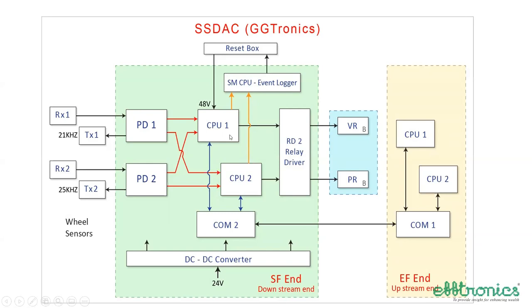CPUs. So CPU 1 and 2 of one end are communicating with the CPU 1 and 2 of the other end through the modems. When both the CPUs count equal in and equal out, the relay driver card gets the message from both of them and it picks up the vital relay, VR. So the count starts from RX coils by the signals given by the TX coils.